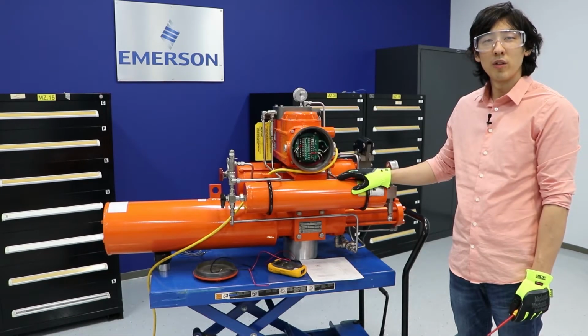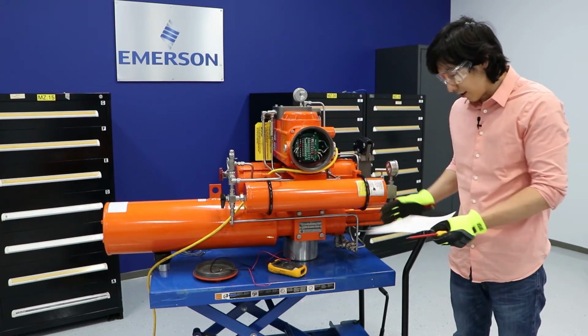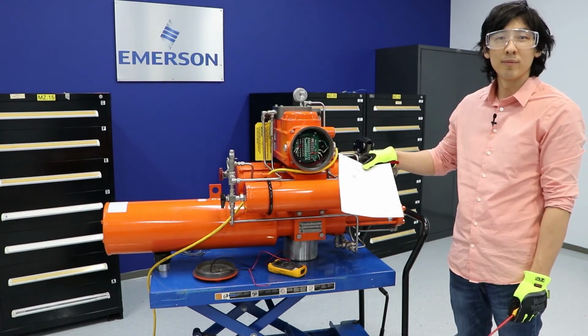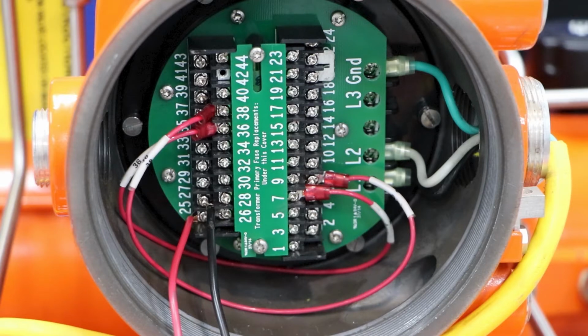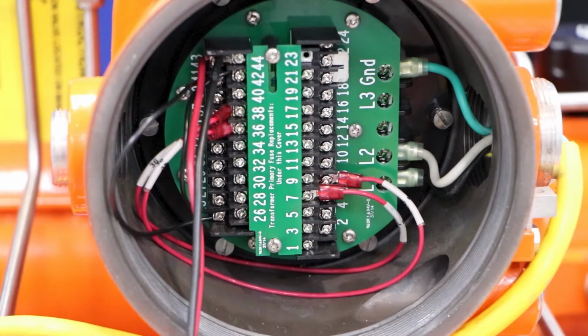Before we get started with the wiring for the analog calibration, make sure you determine whether your analog input is either with or without HART. Make sure you reference your wiring diagram to determine which setup you have. If you are doing analog input calibration without HART, you will apply the positive terminal of your current source to terminal 25 and the negative terminal of your current source to terminal 26. If you are doing analog input calibration with HART, you will apply the positive terminal of your current source to terminal 43 and the negative terminal of your current source to terminal 44.